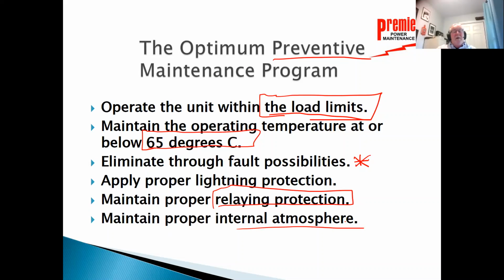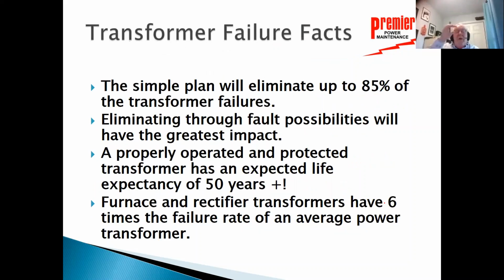atmosphere. So if I look at this, the three that I want to look at: I want to make sure that I operate it within the load limits. I want to make sure that I do my best to eliminate any fault possibilities. I want to make sure that my relay system works, and I certainly want to make sure the internal atmosphere of that transformer is always carefully maintained. So if we can follow this simple plan, we will eliminate up to 85% of the transformer failures that we typically have.